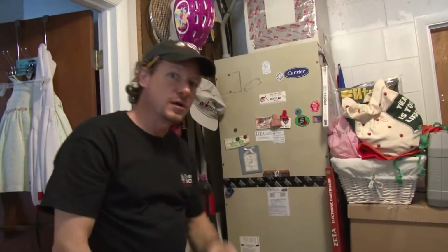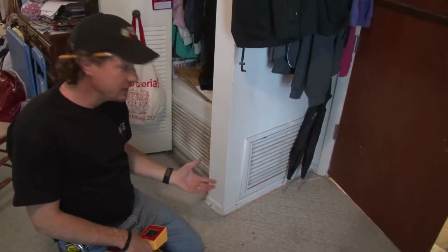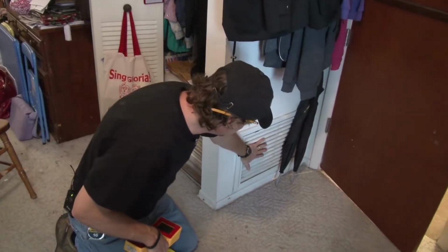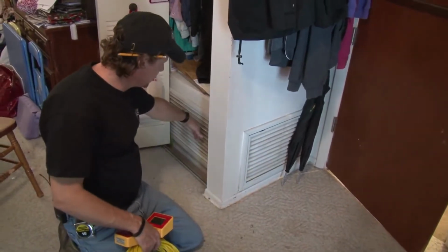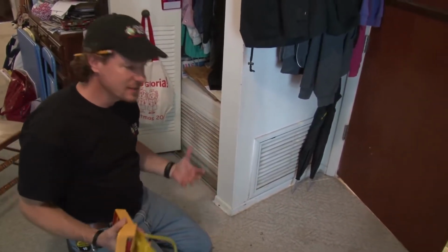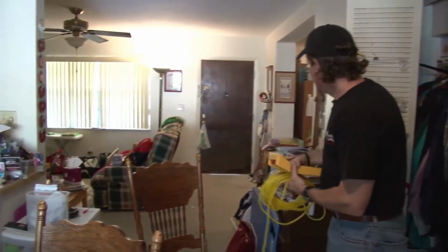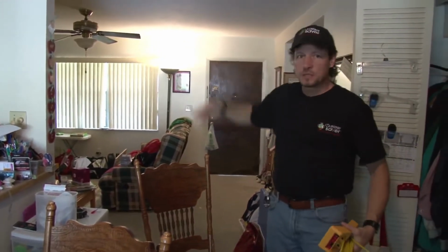Let's take a look at what the return air duct is doing. Here we are just outside the utility room and we see a return grill here and a return grill here. Well, there's no other returns anywhere else in the house. This means that we are drawing all our return air from these common areas, from the kitchen, from the living room, from the dining room, and from the central hallway. When bedroom doors are closed, we have no return air coming back from the bedrooms.